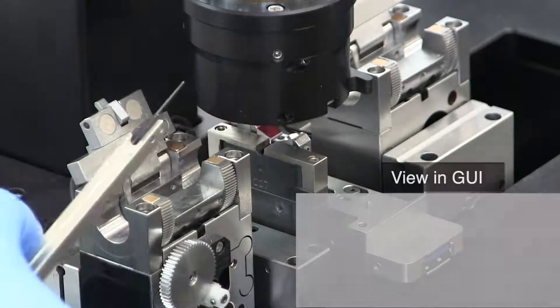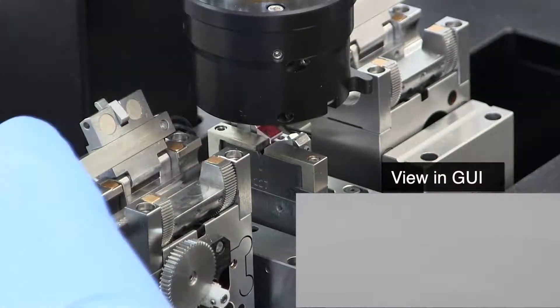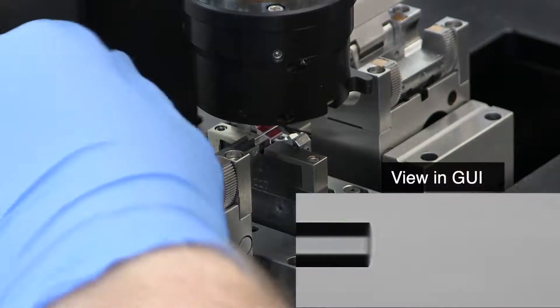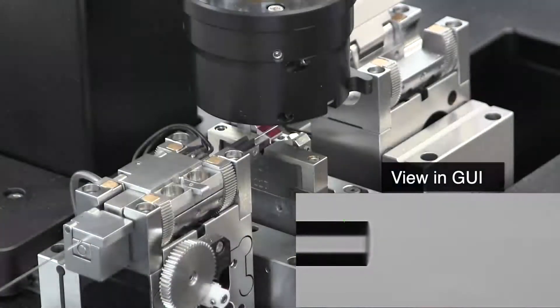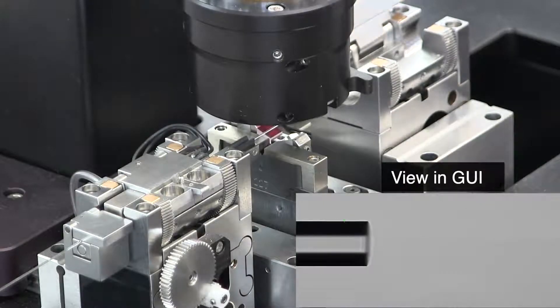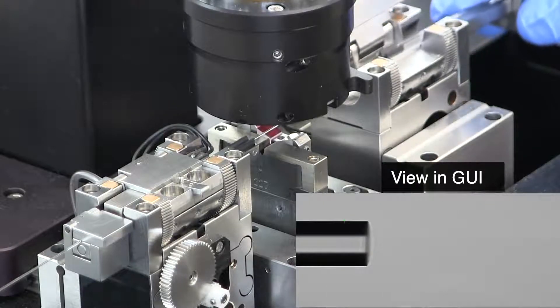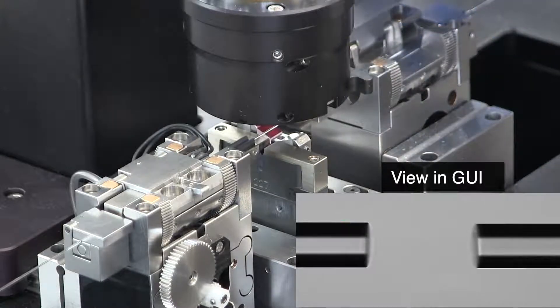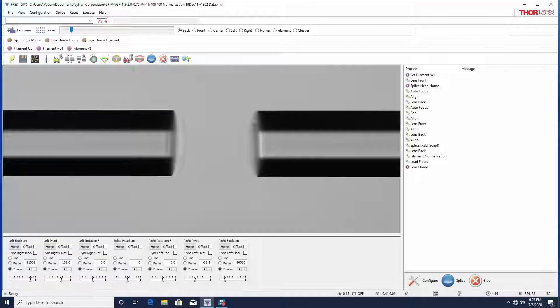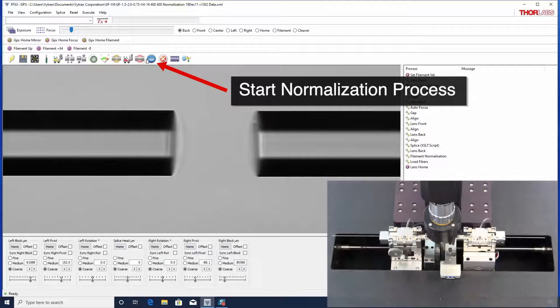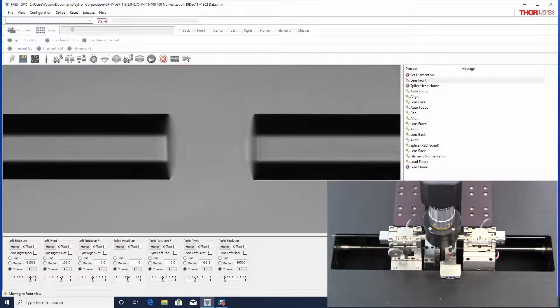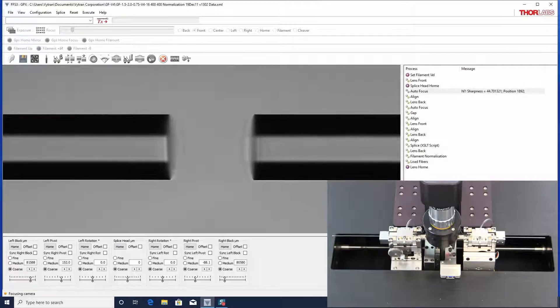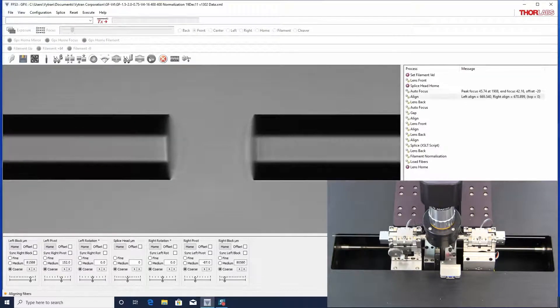To carry out a filament normalization, first prepare two fibers of the required diameter and load them into the fiber holding blocks. Ensure that the correct normalization file is loaded and initiate the splice process by pressing the start button on the unit or in the graphical user interface.